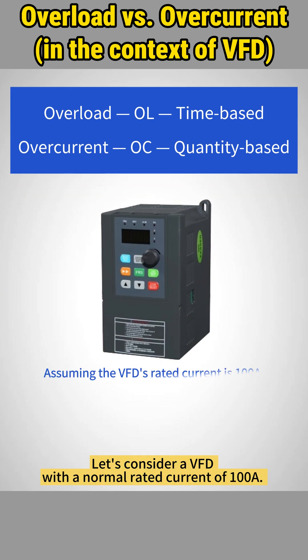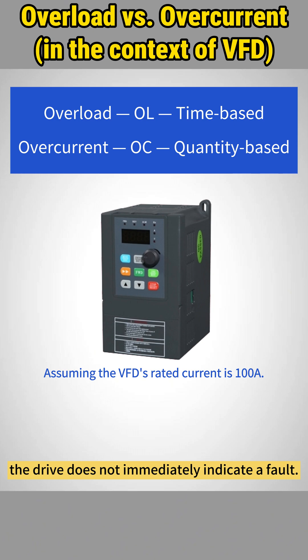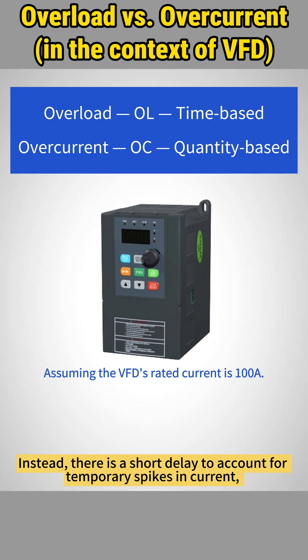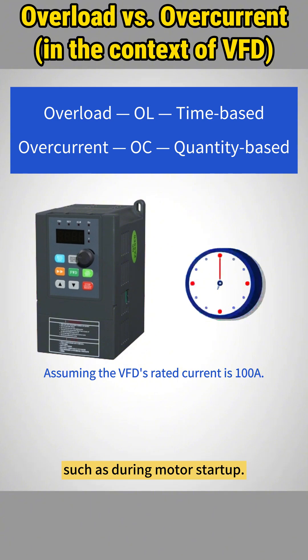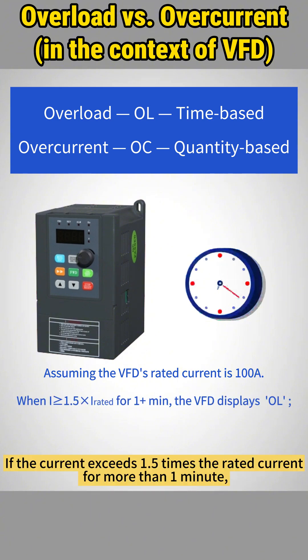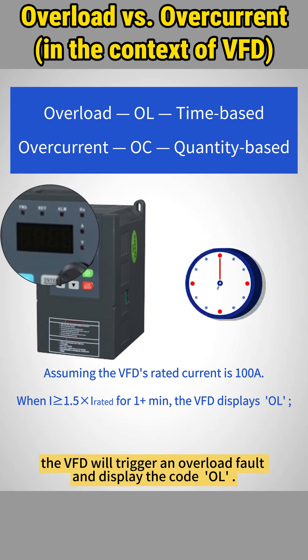Consider a VFD with a normal rated current of 100 amps. When the current flowing through the VFD exceeds the rated value, the drive does not immediately indicate a fault. Instead, there is a short delay to account for temporary spikes in current, such as during motor startup. If the current exceeds 1.5 times the rated current for more than one minute, the VFD will trigger an overload fault and display the code OL.